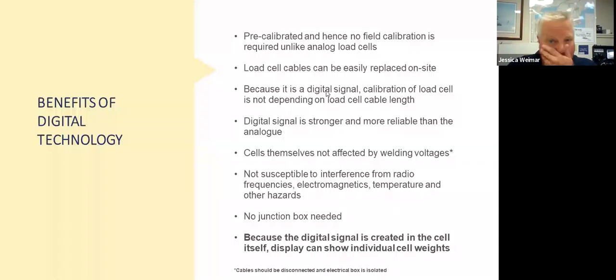So let me jump back here again. So again, the load cells can be changed on site because it's a digital signal. The calibration doesn't change. One of the other things that's needed, the signal itself is a lot stronger. A digital signal is a lot stronger than an analog signal, which means that it can travel longer distances. We can run these cables up to 100 meters away with no effect on performance.